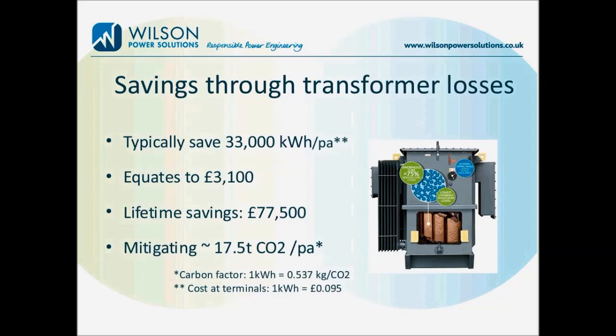So let's just recap here. A super low loss transformer will provide you with guaranteed savings through those reduced transformer losses. So a 1000 kVA unit will typically save £3,100 per year, which equates to a lifetime saving of over £77,000 through the loss savings alone.